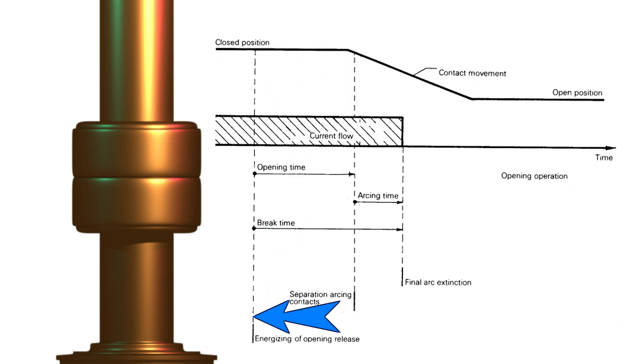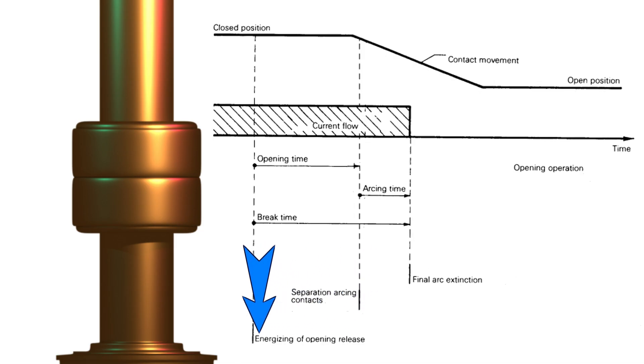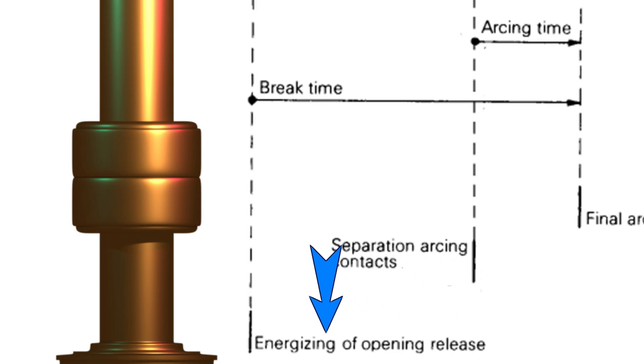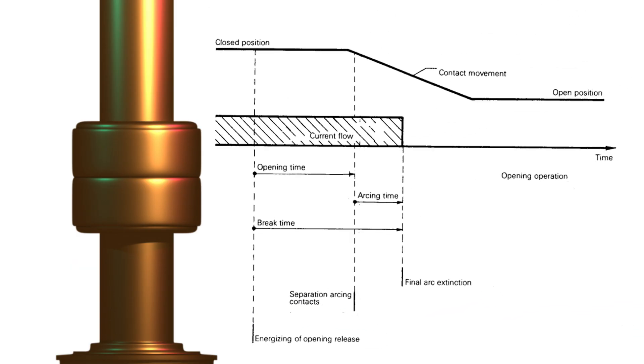Now suppose at that point, the opening release is actuated — the opening release is energized. As soon as the opening release is energized, the breaker will not open immediately because there will be a slight movement of the hinges, levers, gears, and associated latches before the actual opening of the circuit breaker, before the actual movement starts by the moving contact.